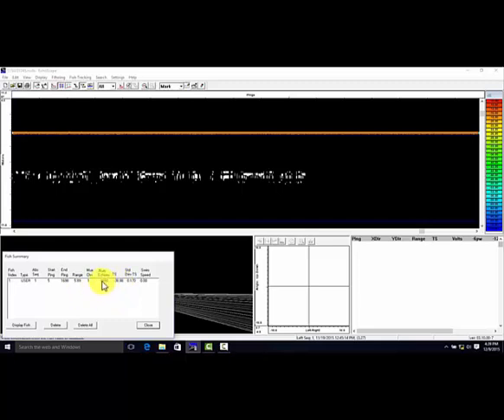Right here I can see I have 1,694 total echoes, which is more than enough. We recommend at least 500. If you can do more than 1,000, that's even better. We just want a number high enough so that these statistics are valid. Right here we see our standard deviation, and mine is 0.170, which is nice and low. So that concludes our test. We've shown you how to set up a sphere calibration in the field, how to collect data for it, and how to take that data back to the office and run it through Echoscape to get your readings of target strength, number of echoes, and standard deviation.